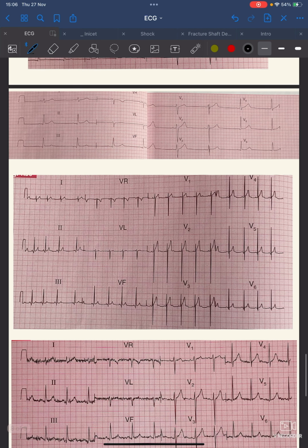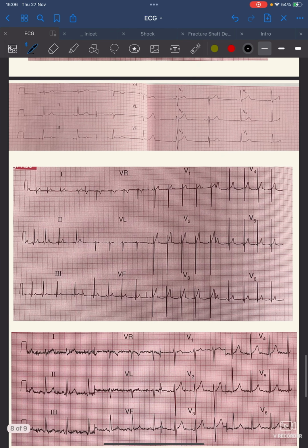The next thing we must consider is that ECG recorders are normally set at a paper speed of 25 millimeters per second. They can be altered to run at a slower speed, which makes the complexes appear spiky and bunched together, or to 50 millimeters per second. The faster speed is used regularly in some European countries and makes the ECG look spread out. In theory, this can make the P wave easier to see, but in fact flattening of the P wave tends to hide it, so this fast speed is seldom useful. And you can see over here.